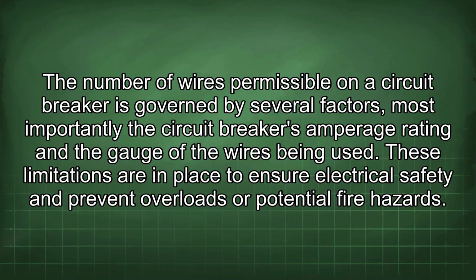The number of wires permissible on a circuit breaker is governed by several factors, most importantly the circuit breaker's amperage rating and the gauge of the wires being used. These limitations are in place to ensure electrical safety and prevent overloads or potential fire hazards.